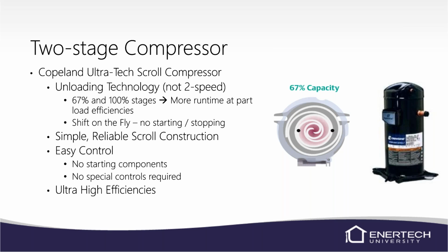The scroll is pretty reliable. Normally, if it fails, there's something else going on in the system. Now, I'm not saying that compressors don't just fail, a motor or something like that, but usually there's an issue behind that, whether it's shipping damage, it fell over in shipment, or it just wasn't made quite properly. But normally there's going to be an issue, whether it be refrigerant or water flow, that's causing the compressor to run higher amp draws and running hotter than normal, things like that. Again, no starting components, no special controls, and it's ultra high efficiency.